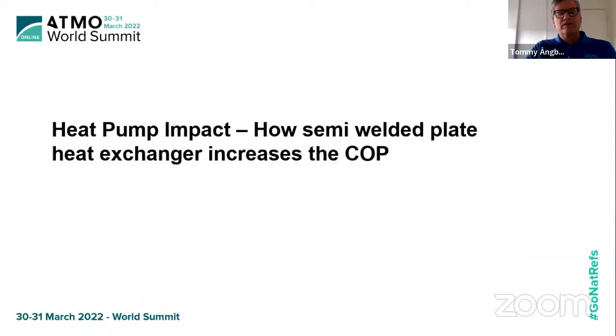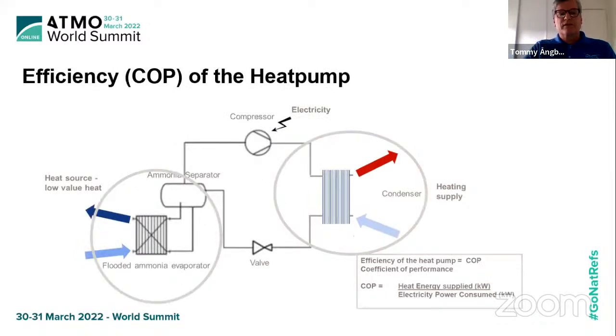Okay, how can the semi-welded plate heat exchanger assure and further increase the COP? First, we must look at the positions of the heat exchangers. The most important two positions are the cold side, where you have an ammonia evaporator with the heat exchangers, and then you have the hot side, where you do the heating supply, as a condenser we can call it in this case. But this machine is not run for free. We load the compressor with electric power.